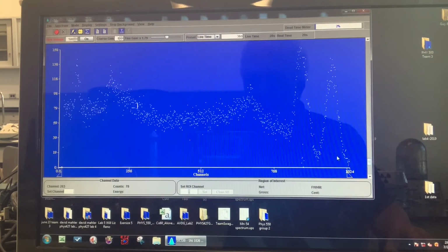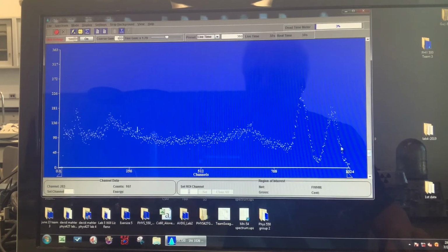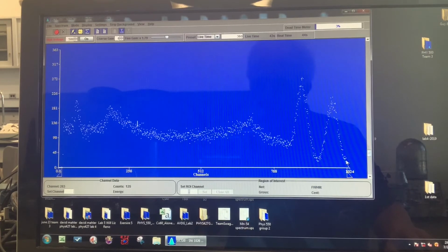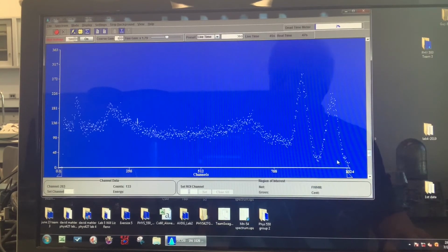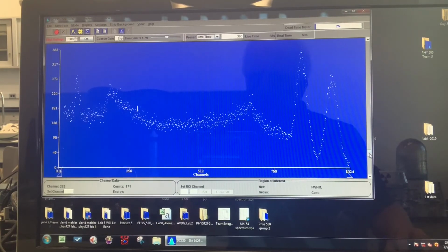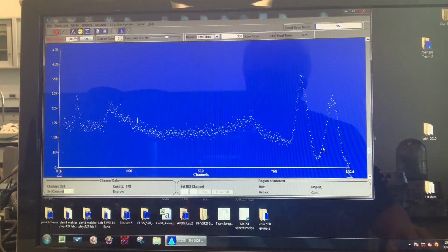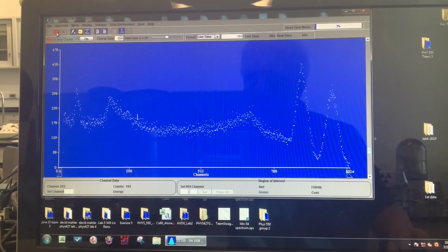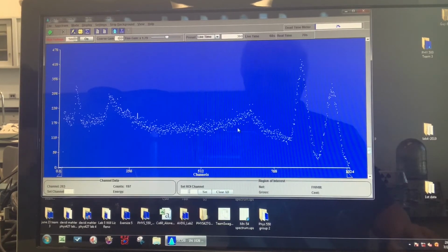Notice I still need to measure the resolution here, so I need to get the whole gamma spectrum, and so if I had picked a higher gain, I would only have half of this Gaussian looking peak in the channel. So I've got the full peak here, so this is actually a pretty good choice of gain. Now, you would count this for a longer time than I'm doing here, but I'm just going to stop it and show you one of the main results of this lab. So I'll stop counting, and we will do a region of interest.